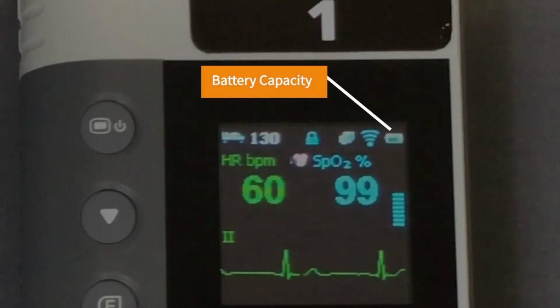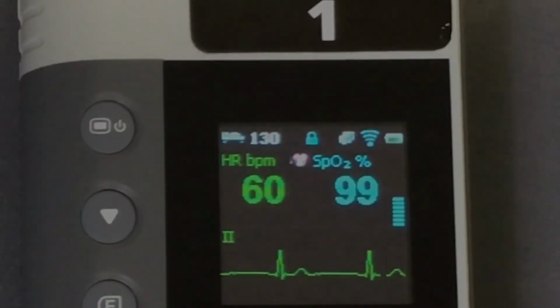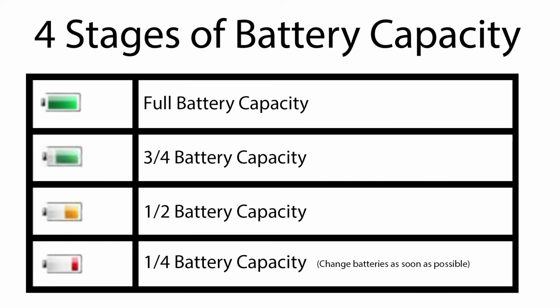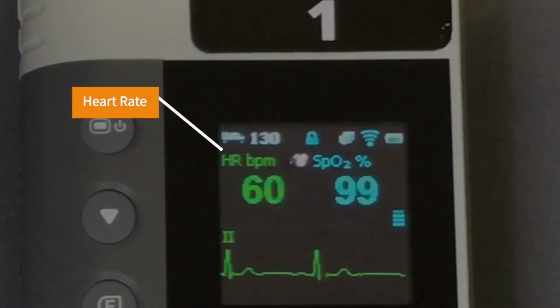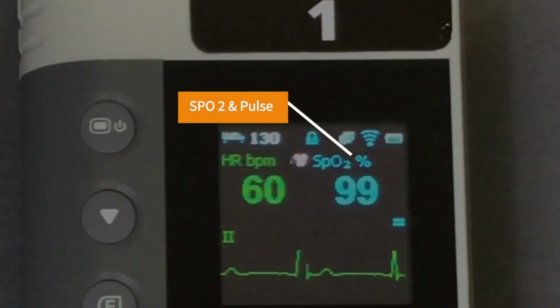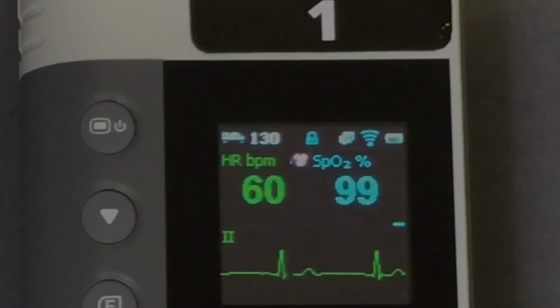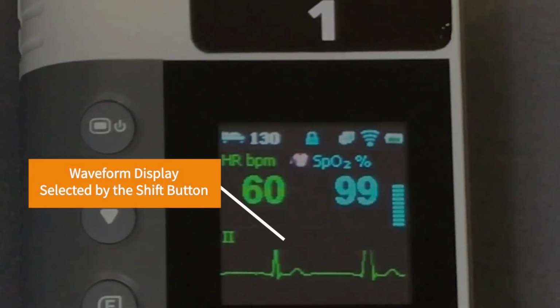And finally, the battery capacity indicator. There are 4 stages to this indicator as you can see in this chart. The battery indicator will change its appearance as the batteries inside the transmitter are used up. You should always change the batteries as soon as you notice the red battery indicator. Below the header we have the vital signs parameters. This number indicates your patient's heart rate. And if your transmitter is equipped with an SpO2 probe, you will see the patient's SpO2 parameter here. Below the vital signs numbers, you will see a waveform display. This waveform is customizable, and can be selected by using the Shift button.